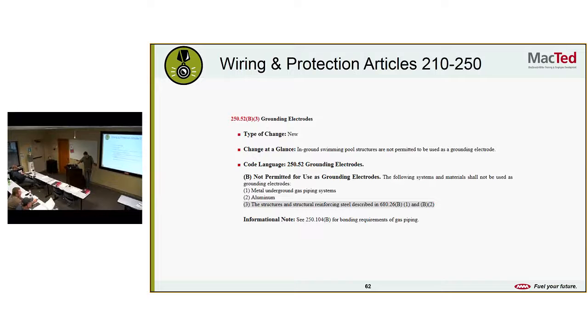We've got a new code for grounding electrodes. In-ground swimming pool structures are not permitted to be used as grounding electrodes. That makes me feel better. It looks like that's probably been a code, but what they added is that the structure and structural reinforcing steel can't be used as a grounding electrode. So the rebar in the concrete of the swimming pool can't be your grounding electrode anymore.